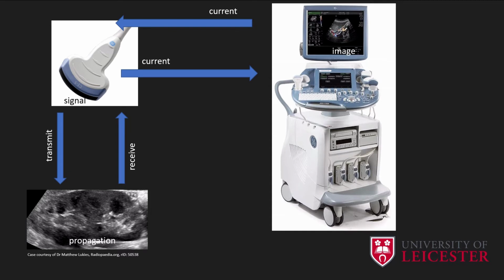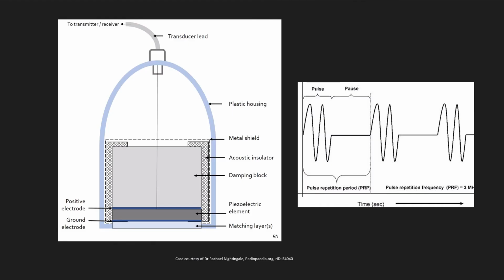What we need to do now is have a look at the transducer in a bit more detail and how it works its magic, which is otherwise known as the piezoelectric effect. We have already established that the crystals, or collectively the piezoelectric element, vibrate and produce a transmit-receive signal. This, however, isn't constant. The crystals transmit a brief pulse of sound and then pause to listen for the receive or reflected signal. This is called the pulse repetition interval, or PRI. The number of pulses and pauses per second is called the pulse repetition frequency, or PRF. This pulse pause allows the machine to calculate how long each echo takes and therefore interpret this as depth. There can be some miscalculation of this, which we'll talk about in the artifacts part of the presentation.